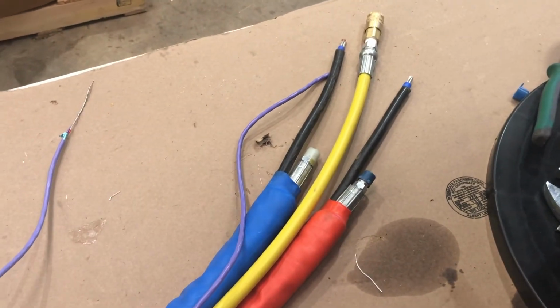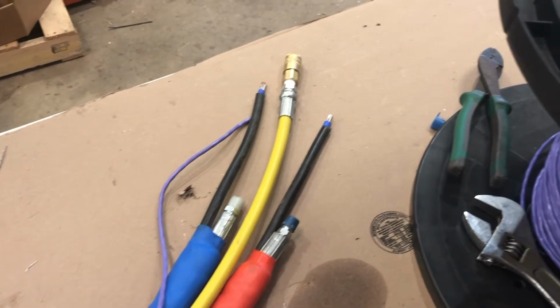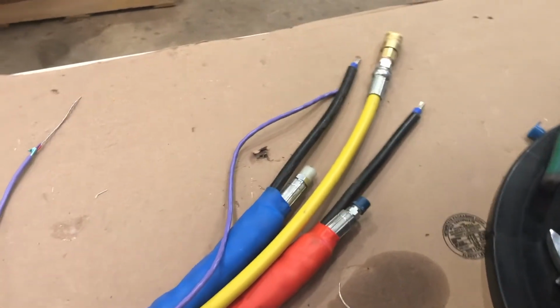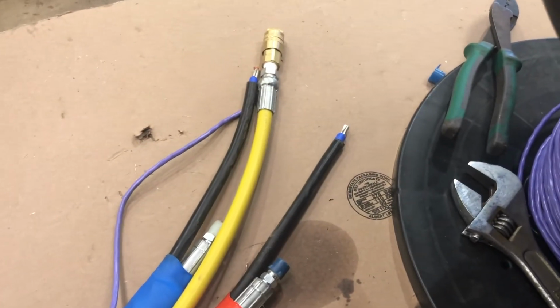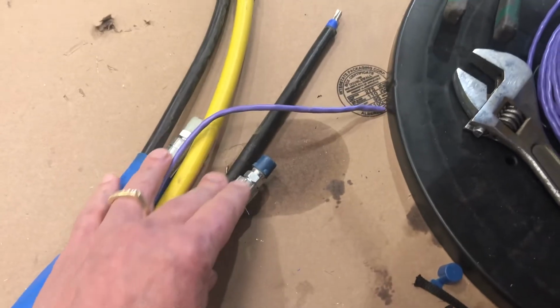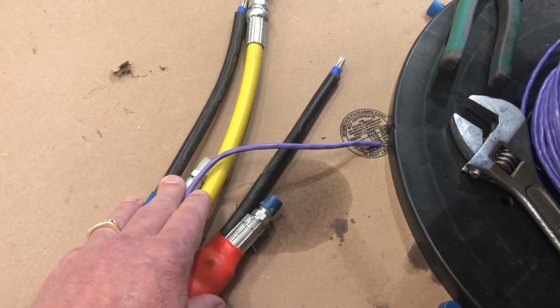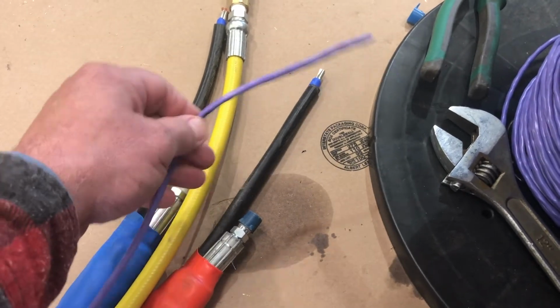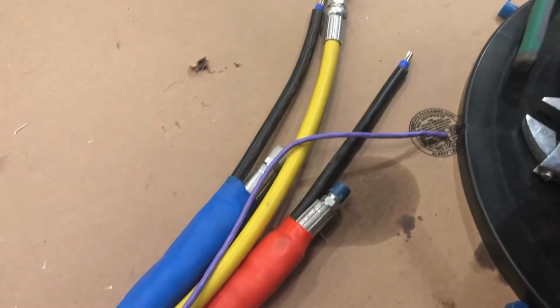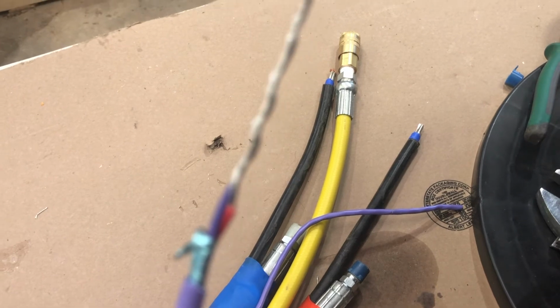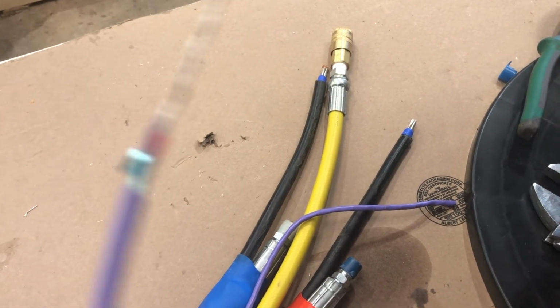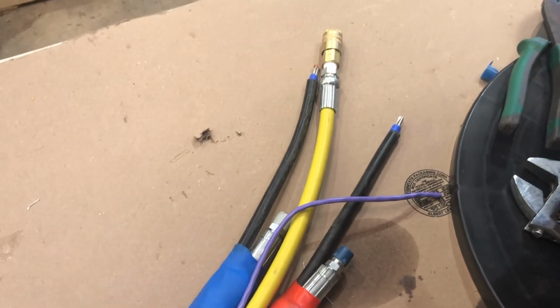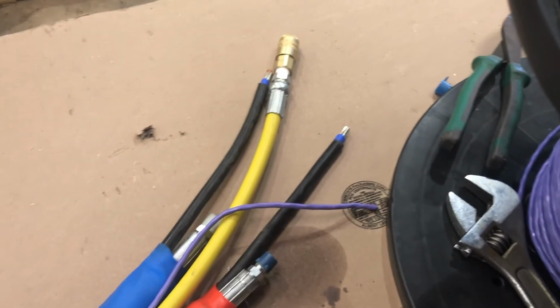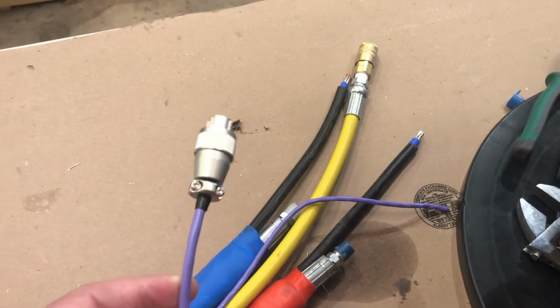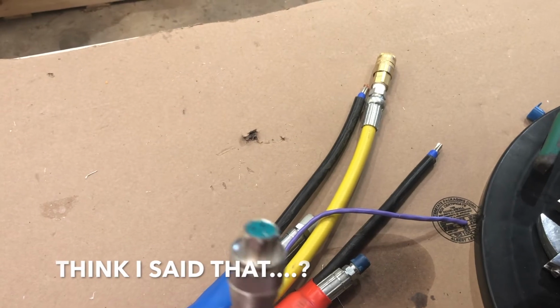If you get an error code on your rig, a lot of times it's going to be the sensor. What we're doing now, if this was a connection point - let's say this was the end of the 50 - which would be a connection point, we just hardwire these if we're building the rigs here. So we take this, strip it back to the red and purple, and connect the red to red and purple to purple, and that's how we go from hose to hose, and we hardwire that. We don't use the 3-pin connectors because it's just another thing to break.